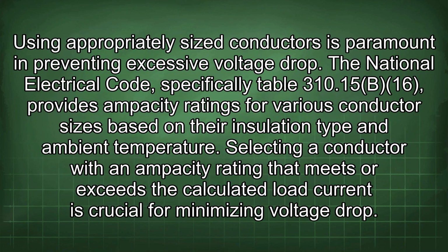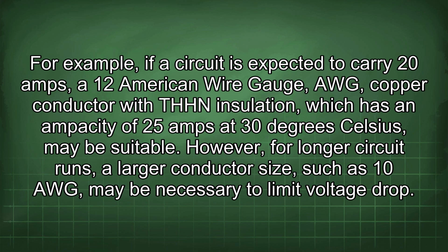Using appropriately sized conductors is paramount in preventing excessive voltage drop. The National Electrical Code, specifically Table 310.15(B)(16), provides ampacity ratings for various conductor sizes based on their insulation type and ambient temperature. Selecting a conductor with an ampacity rating that meets or exceeds the calculated load current is crucial for minimizing voltage drop. For example, if a circuit is expected to carry 20 amps, a 12 American Wire Gauge (AWG) copper conductor with THHN insulation, which has an ampacity of 25 amps at 30 degrees Celsius, may be suitable. However, for longer circuit runs, a larger conductor size, such as 10 AWG, may be necessary to limit voltage drop.